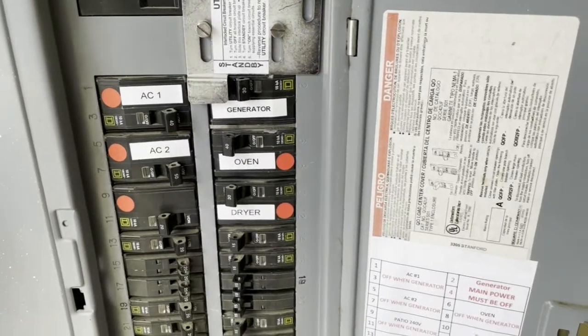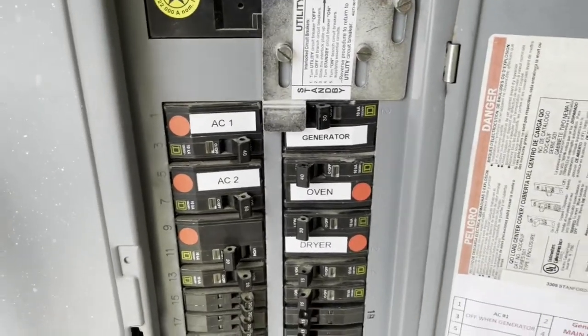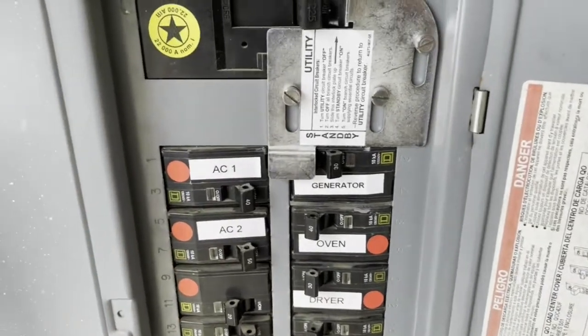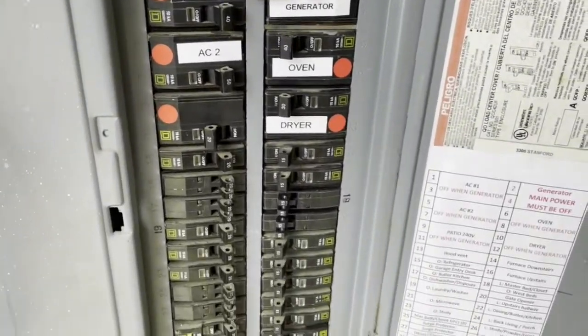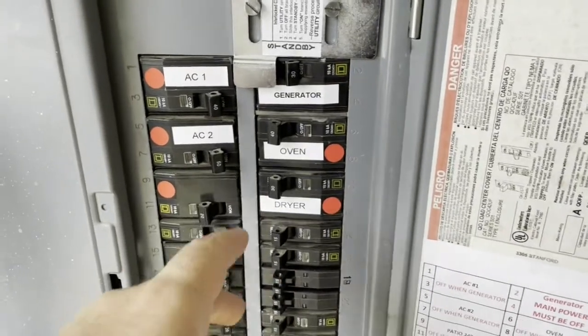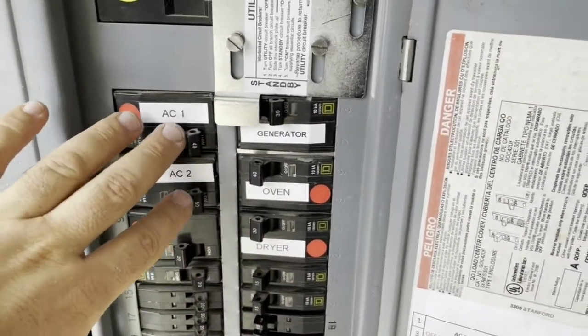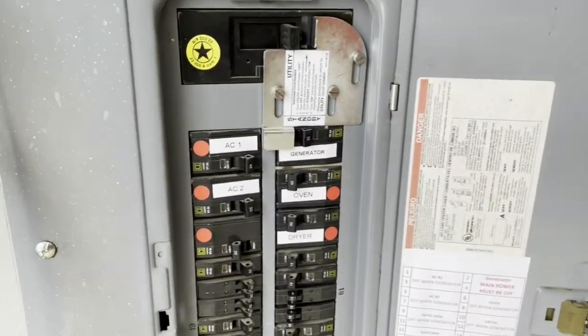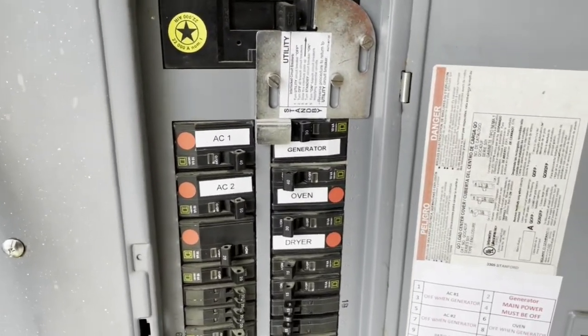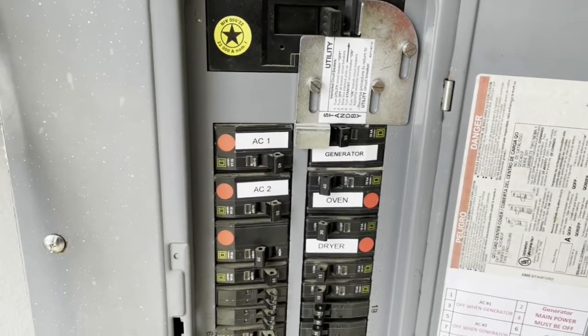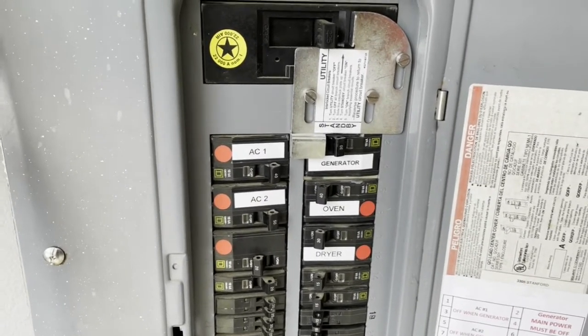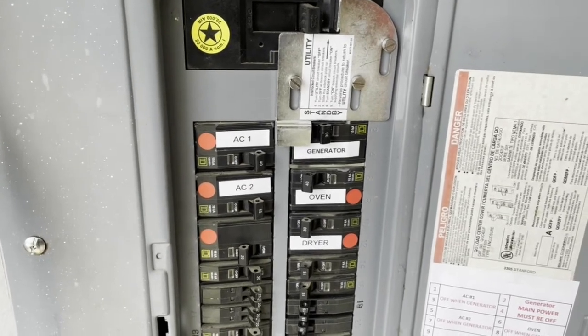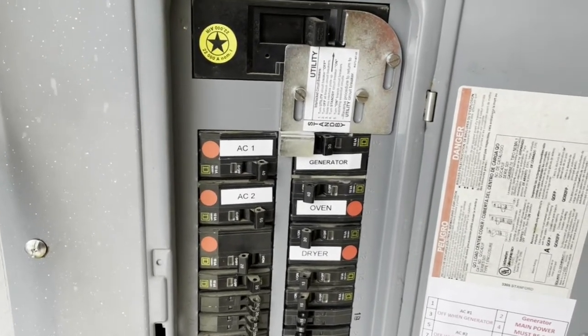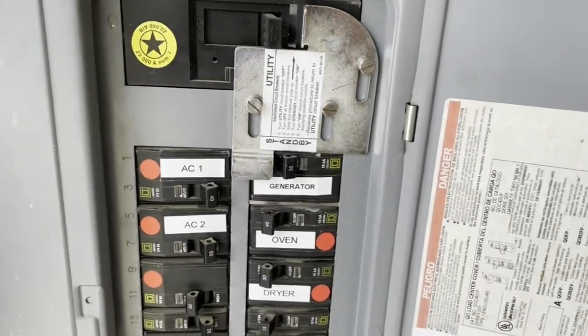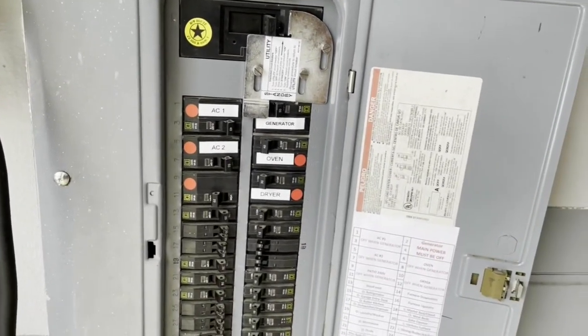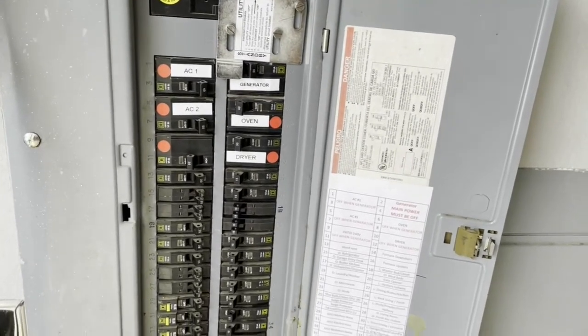First of all, I don't think I would need a dryer in an emergency situation. AC is debatable. I mean, you can still live without it. But they are very high load, so you should always keep them off. If you overload the generator, two things will happen. First of all, it will give an alarm and it will cut off the whole power. If not, then your voltage will drop, your frequency may change, and you can create damage on your electronics and other stuff. So it's very important to keep the power in control.